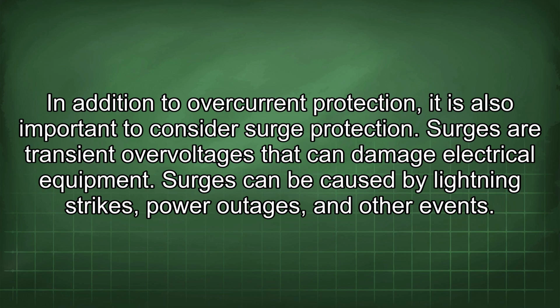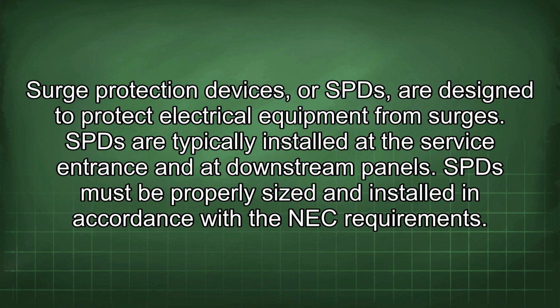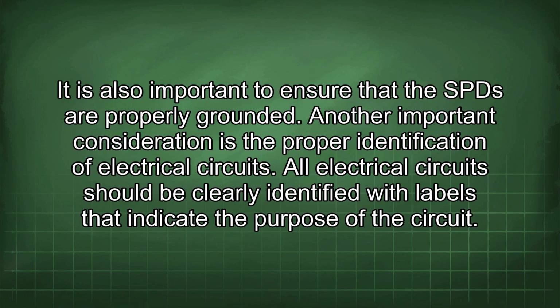In addition to overcurrent protection, it is also important to consider surge protection. Surges are transient overvoltages that can damage electrical equipment. Surges can be caused by lightning strikes, power outages, and other events. Surge protection devices, or SPDs, are designed to protect electrical equipment from surges. SPDs are typically installed at the service entrance and the downstream panels. SPDs must be properly sized and installed in accordance with the NEC requirements. It is also important to ensure that the SPDs are properly grounded.